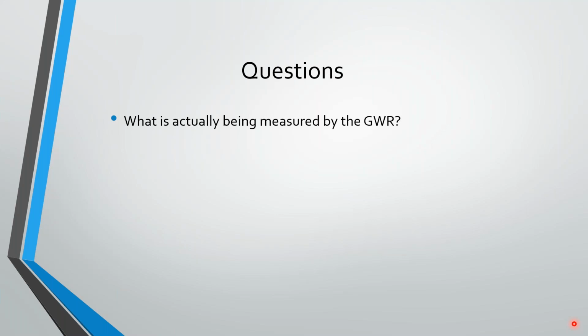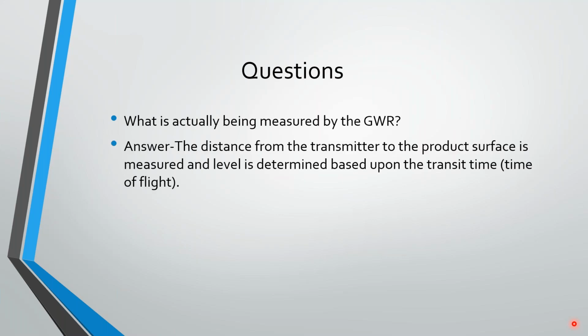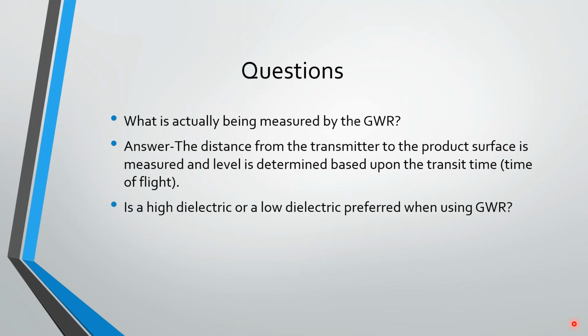I'll give you the answer. We're actually measuring the distance from the transmitter to the product surface. We're looking at the transit time, also known as time of flight, and from that we determine where the level is, because when we programmed the device, we told it what the full travel distance was, so it's able to do some math and figure out where the level's at.